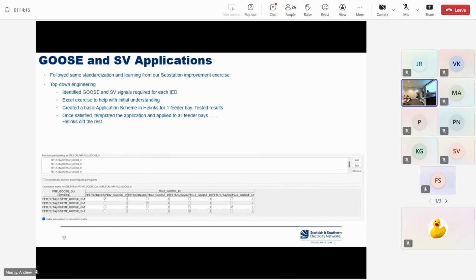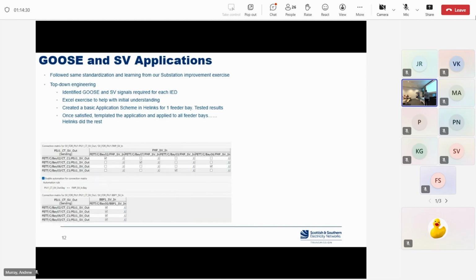We then added Bays 3, 2, and 6. By just checking the box here, Helinks is able to do the rest based on the application you've taught it from the initial deployment, and build the rest of the Goose messages for you. It's the same for the sampled values, where we have tick boxes between PIU1 and the bay, and also for the busbar protection, where we're sending sampled values from the bay to the main busbar protection IED.